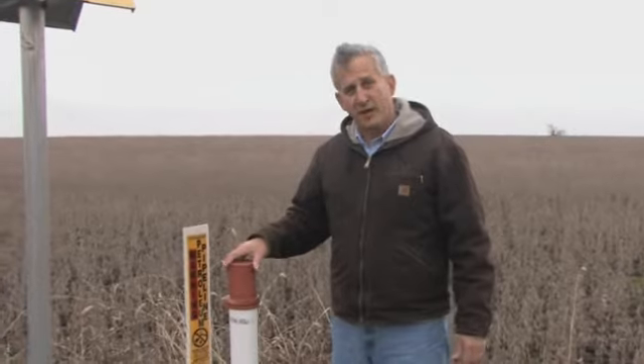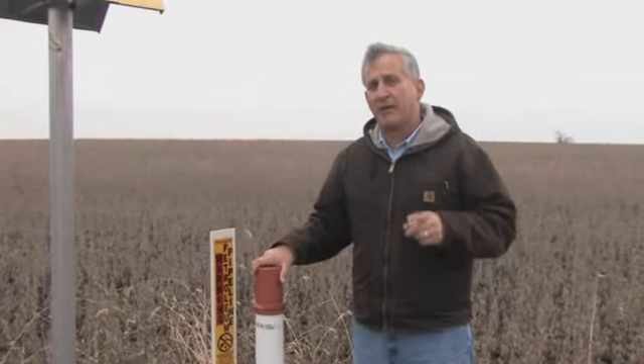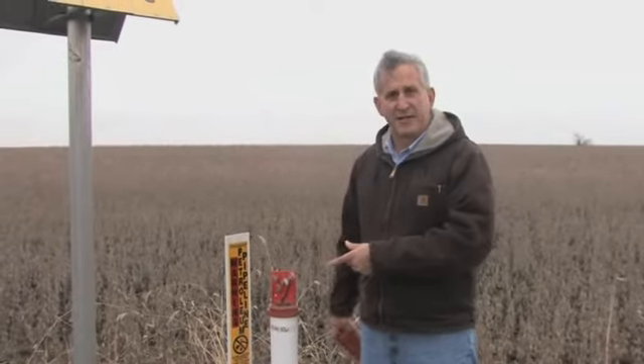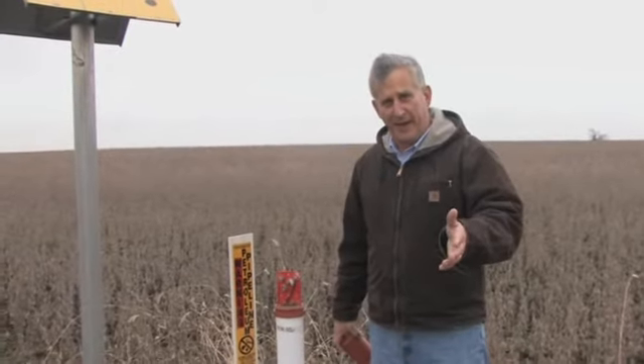This is a test station. It's a place where the corrosion technician for the pipeline company will test the effectiveness of the cathodic protection system. But it's also a place where the pipeline locating technician can come with his instrument and apply a signal to the pipeline so it can be located in front of excavation.